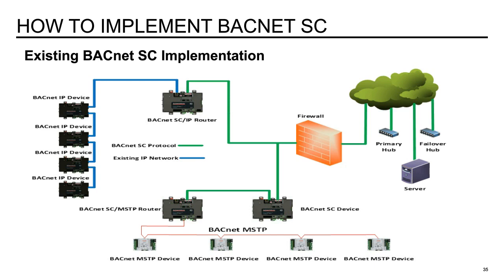And in the case at the bottom where you have the BACnet MSTP link, you would just put a BACnet SC to MSTP router and then connect out from the BACnet SC router, and then this network would be secured from the BACnet SC router out. One thing I do want to point out is if you do have a system that has existing BACnet IP devices, you don't necessarily have to put in an SC to IP router for every BACnet IP device. You can put one BACnet SC to IP router for all of these devices.